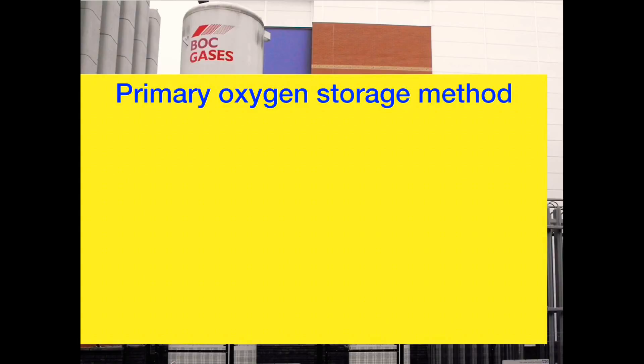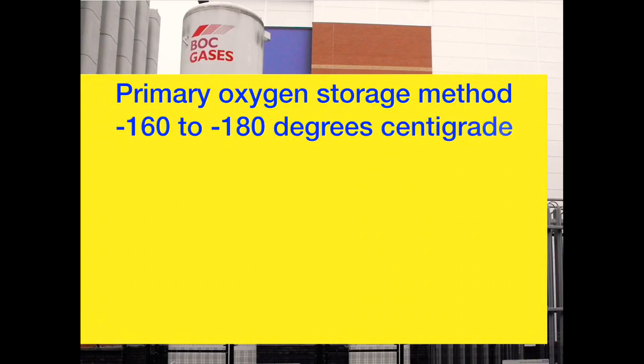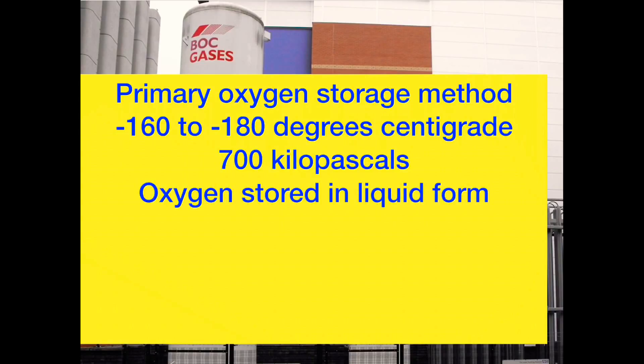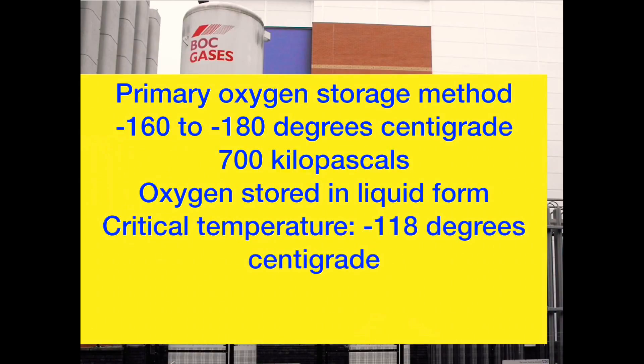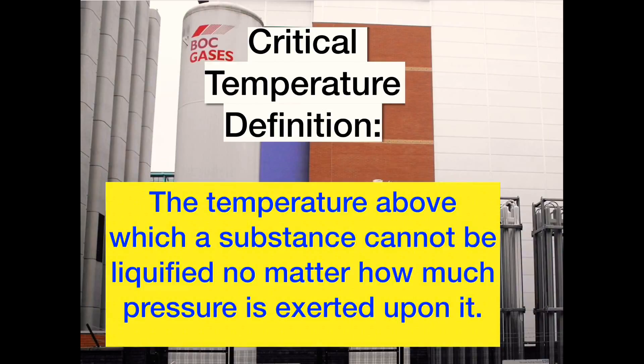The VIE is the primary method of storage in larger hospitals. It is kept at a temperature between minus 160 and minus 180 degrees centigrade. At these temperatures and a pressure of 700 kilopascals, the oxygen is stored in a liquid form, allowing more efficient use of storage volume. Oxygen has a critical temperature of negative 118 degrees centigrade, so it is mandatory that the oxygen be cooled below this to be stored as a liquid.